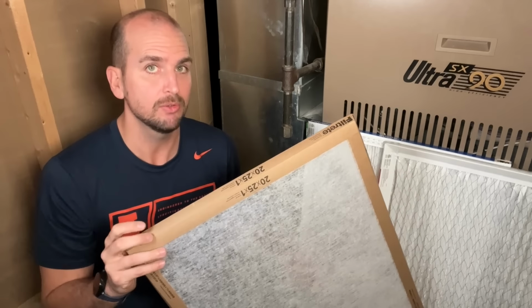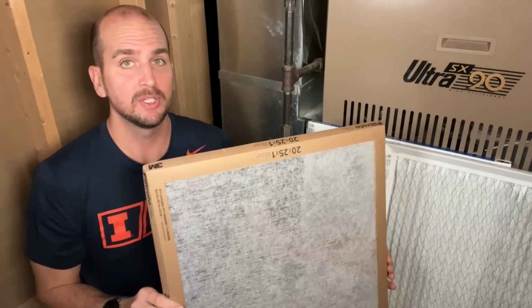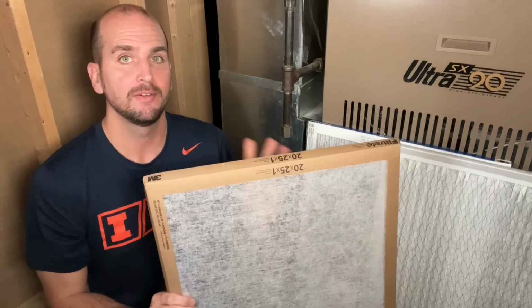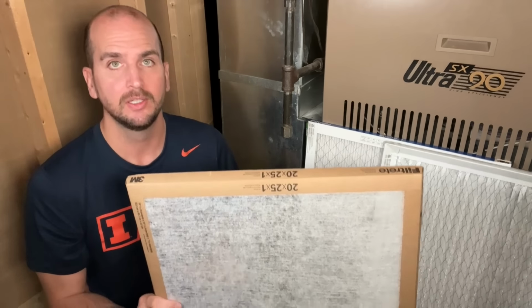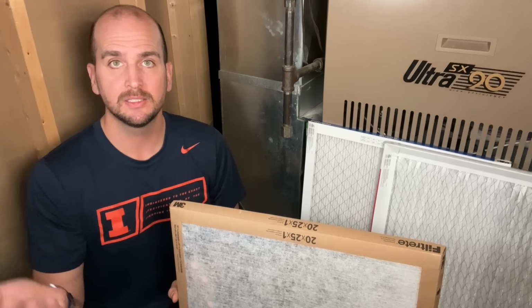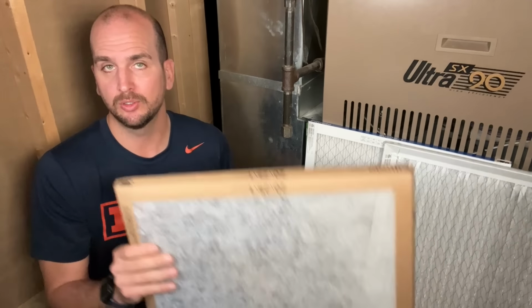If you can see through the filter, you can guess how little it's actually removing from the air. The only advantages of this type of filter are, one, cost, and two, it has very little restriction. It doesn't restrict the air going through your unit, so it's easier for your unit to properly heat, cool, and maintain humidity in your home. So there's a balance you want to maintain between removing particles from the air, especially if you have allergies, and not putting too much restriction on your unit.